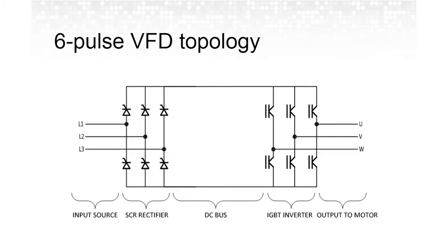Basically, the harmonic distortion associated with cheaper 6-pulse VFD designs could be up to the 80% range. Even after adding mitigation like line reactors, this harmonic distortion can still be in the 30% range. The IEEE standard for harmonic distortion has a total harmonic distortion limit of 8%, and depending on what percentage of overall load is represented by VFDs on an electrical service, this can be an incredible power quality issue.